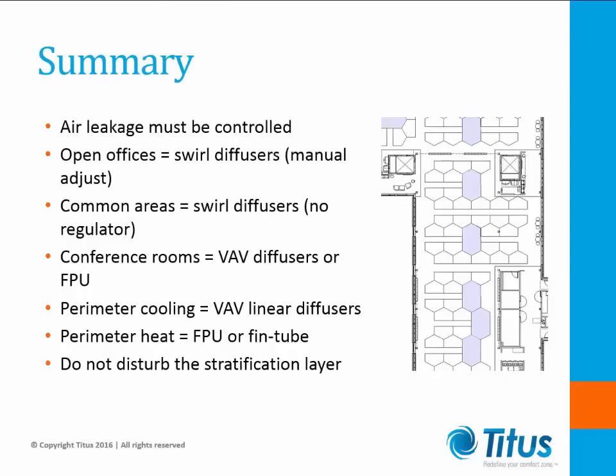To summarize what we've covered today about UFAD systems: Air leakage can be a major issue if not handled correctly. Open offices are best handled with swirl diffusers, while common areas are best handled with swirl diffusers without regulators. Conference rooms are best handled with actuated diffusers or fan-powered terminals. Perimeter cooling is best handled with VAV linear diffusers. Perimeter heating can be handled by fan-powered terminals, but fin-tube would be better. Perimeter diffusers must not disturb the stratification layer.